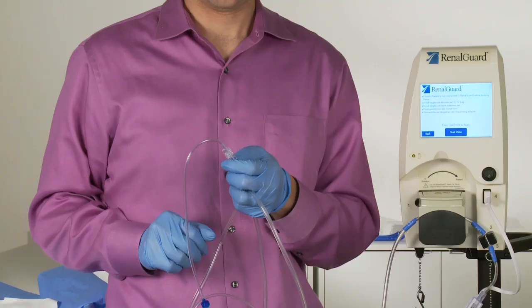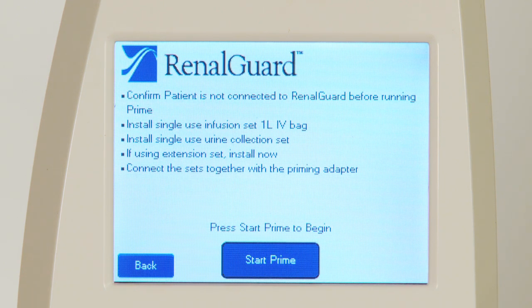On the urine collection set side, the bag is hanging freely from the plastic hook, and the tube is installed correctly in the chain guide with the bumblebee. The bag is tucked inside the bag guard, and the urine bag is closed. Lastly, the priming adapter is connected to the Foley adapter and the infusion set. You're ready to prime. Once your set is correctly installed, drape the tubing on the console to prevent it from dragging on the floor and touch Start Prime to begin priming.